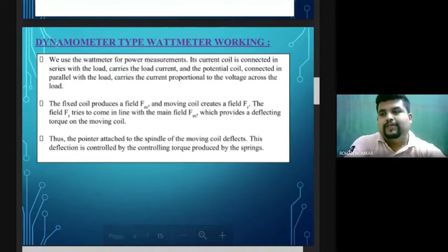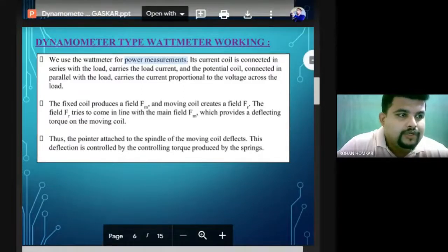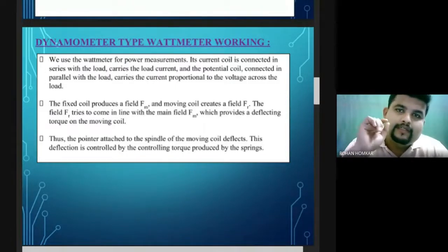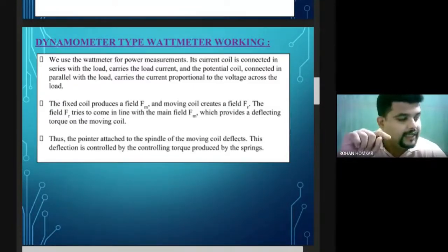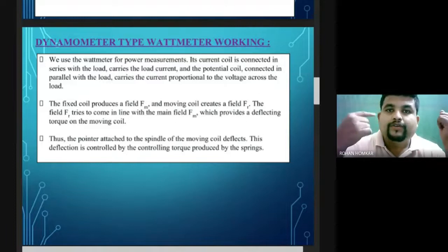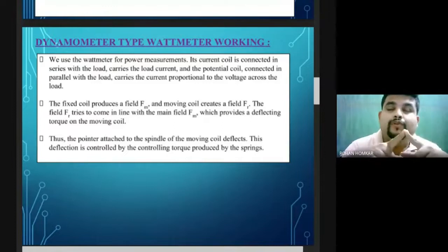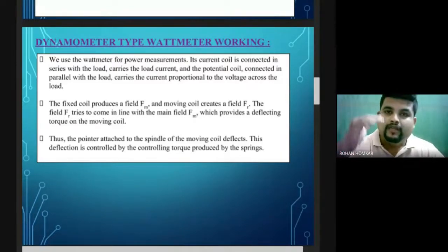For power measurement using the dynamometer type wattmeter: the current coil is connected in series with the load and carries the total load current. Since the current value is higher, the fixed coil has a larger diameter and fewer turns. So the fixed coil uses a thick wire for winding with a less number of turns.